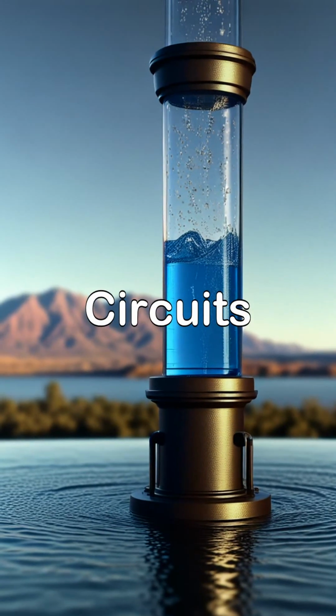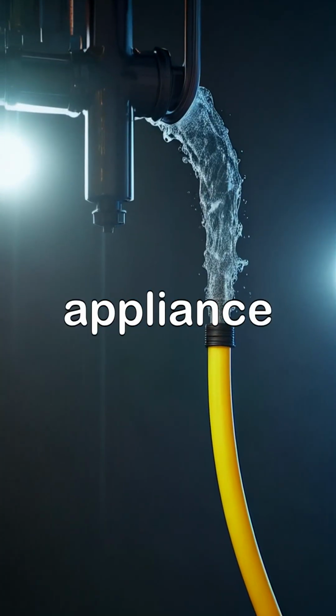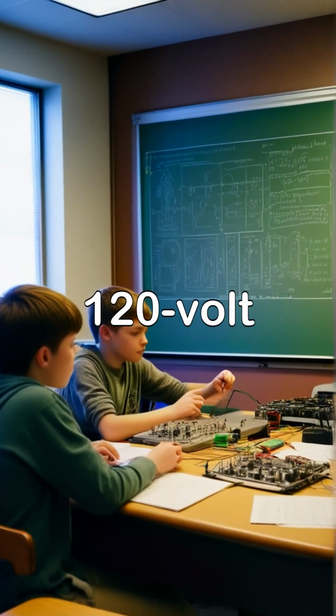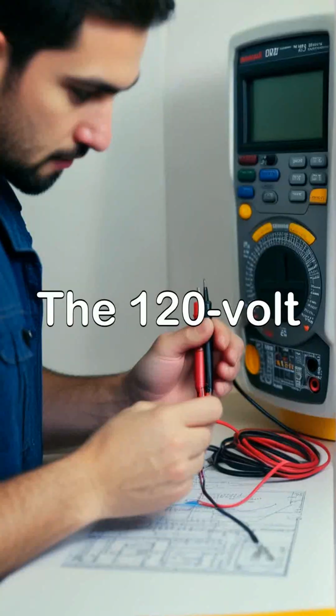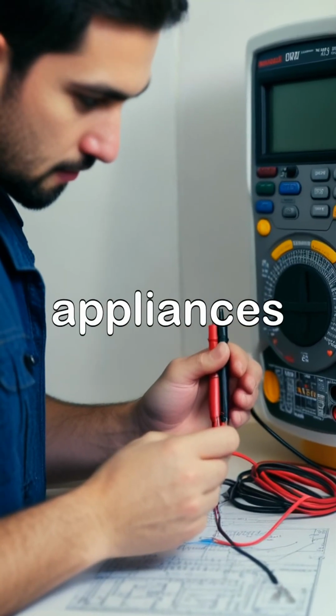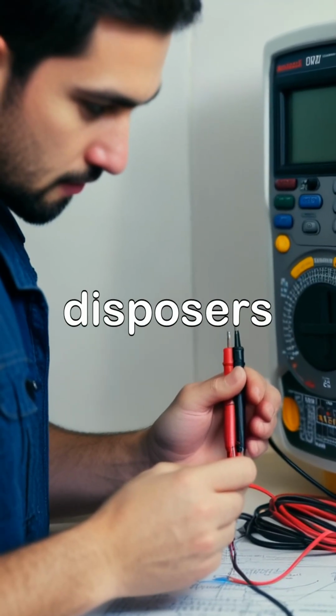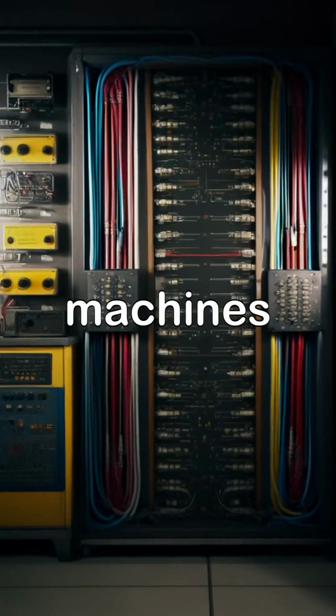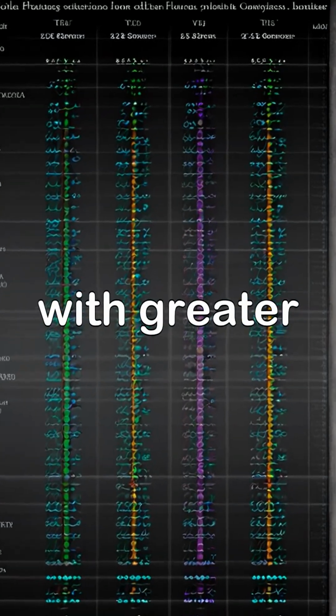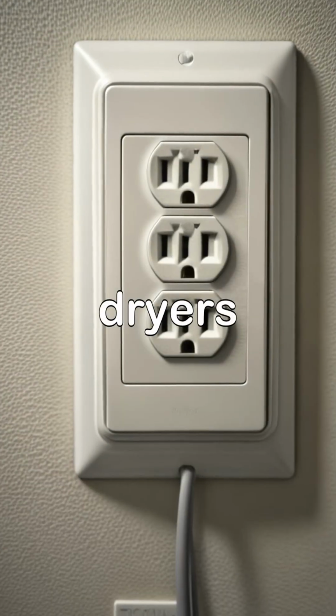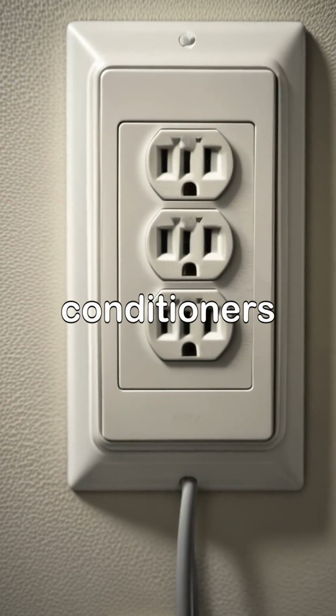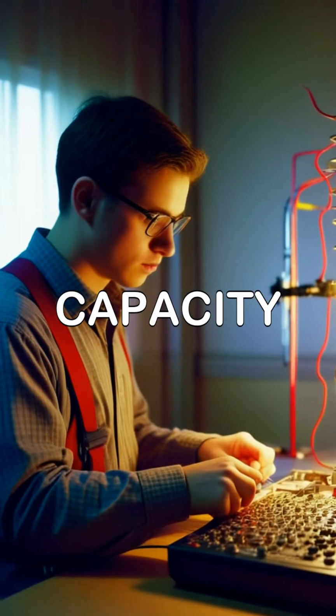Individual branch circuits. These circuits supply only one appliance. There are 2 types, 120-volt circuits and 240-volt circuits. The 120-volt circuits service appliances such as dishwashers, food disposers, trash compactors, and washing machines. The 240-volt circuits are for appliances and equipment with greater power requirements such as clothes dryers, ranges, water heaters, and air conditioners.